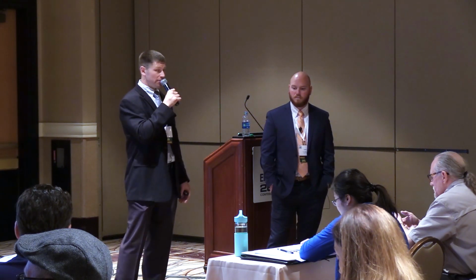But a lot of times what we're in it for is to find energy savings in these facilities. So when we can find those energy savings and we can identify exactly what they have to do, what kind of control setbacks, what do they have to fix, do they have to go back and retab the whole building, and is that going to be enough? Is it go back and recalibrate these sensors? Is it fix all your DDC controls here, or replace this old Falcon system that is out of date?